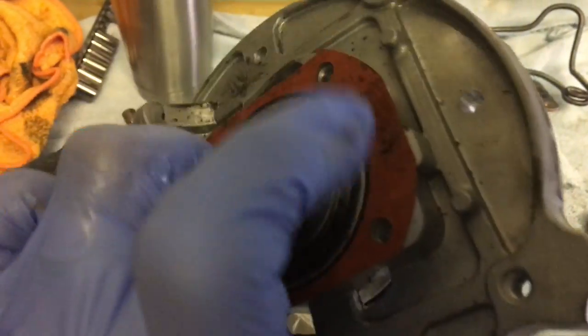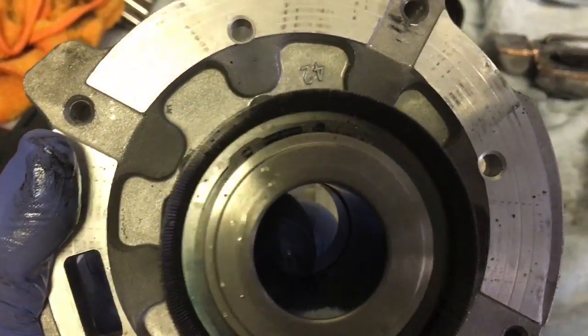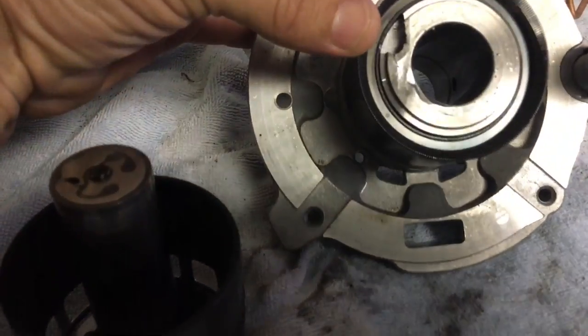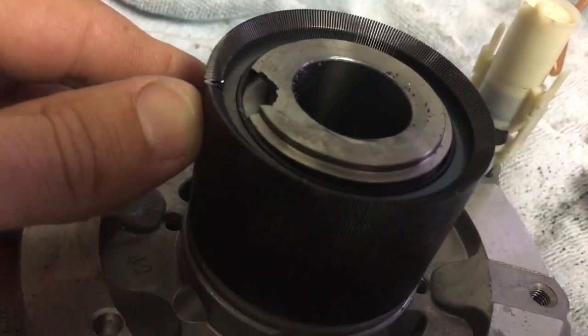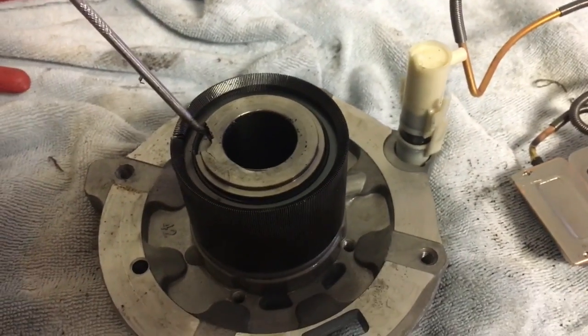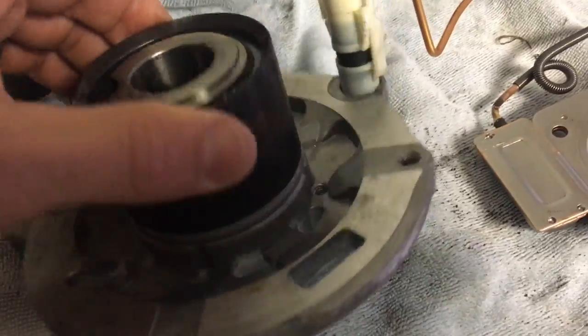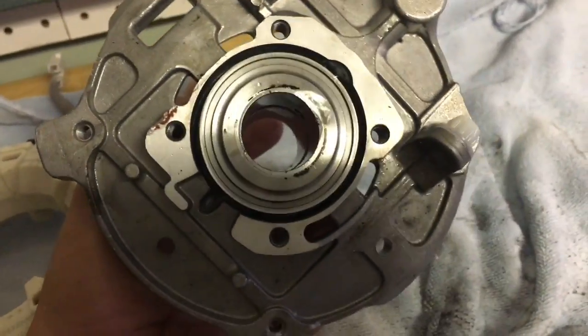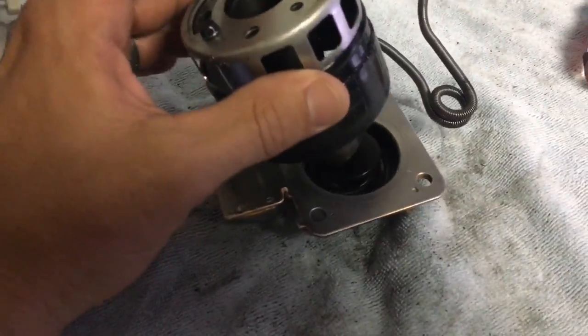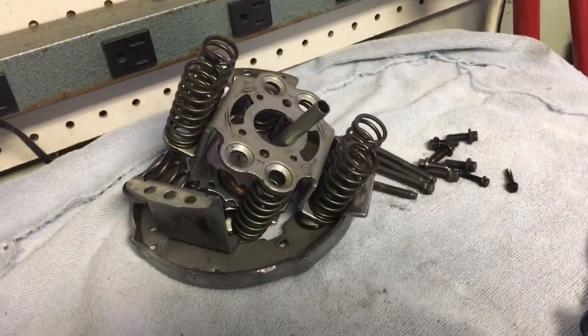There's nothing in here that feels like it's going to move or do anything special, but I did notice there's a couple of retaining clips on here. I'm going to try to get those out and dig further into this. Got the retaining ring out and it looks like it's just in there to hold that second set in place. The part that goes on the outside here is magnetic. That's all back end, this is the middle, and there's your front — that's where your hot gas comes out. It loops in there just to keep the pipe from breaking under normal vibrations.